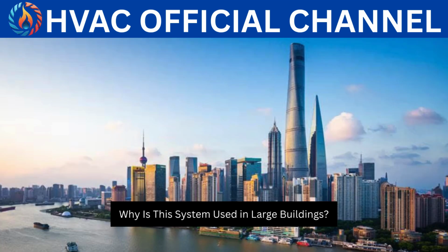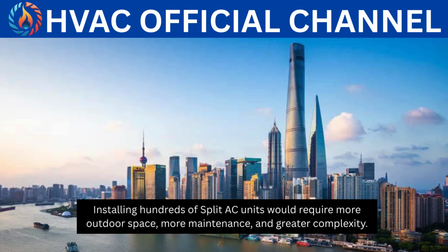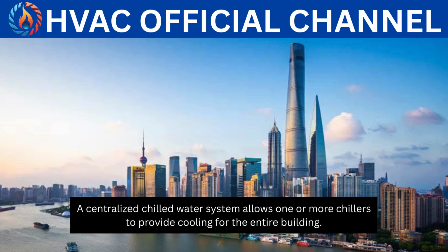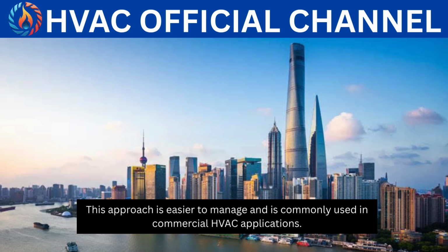Why is this system used in large buildings? Large buildings have very high cooling loads. Installing hundreds of split AC units would require more outdoor space, more maintenance, and greater complexity. A centralized chilled water system allows one or more chillers to provide cooling for the entire building. This approach is easier to manage and is commonly used in commercial HVAC applications.